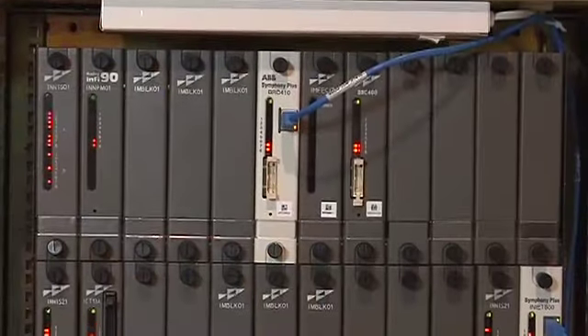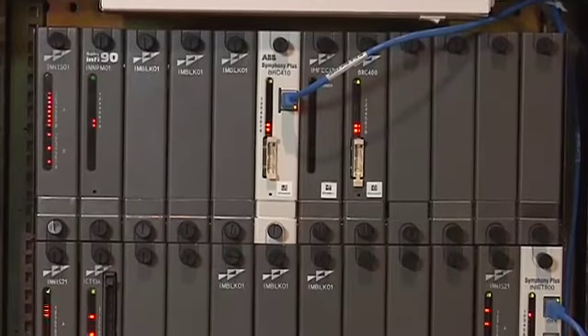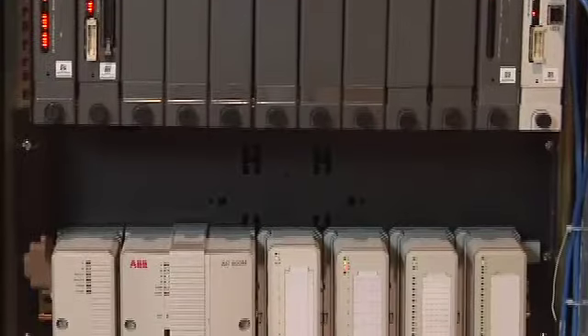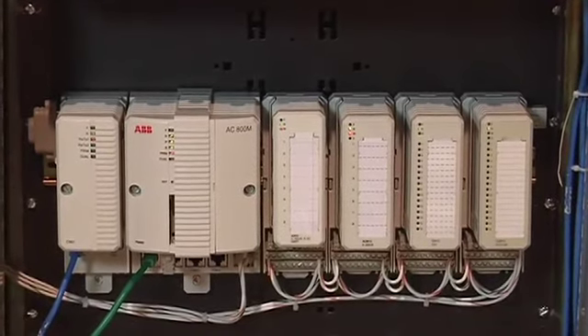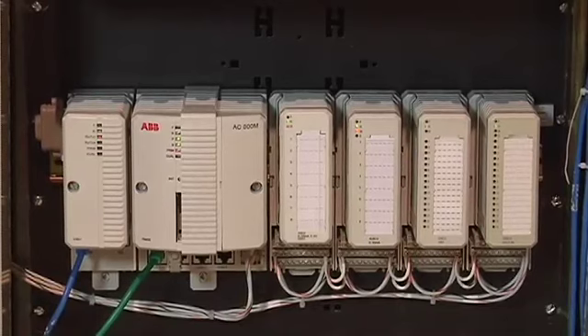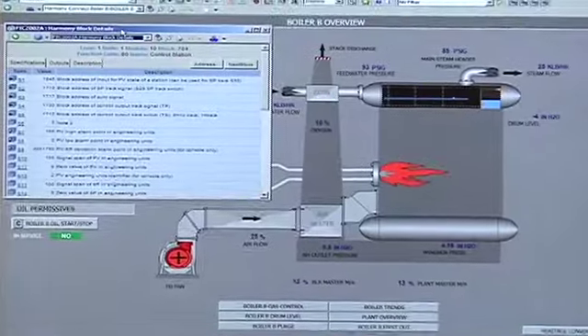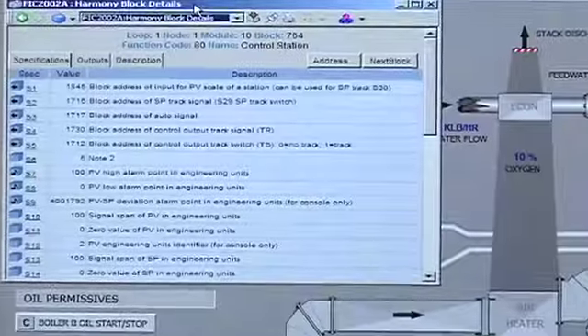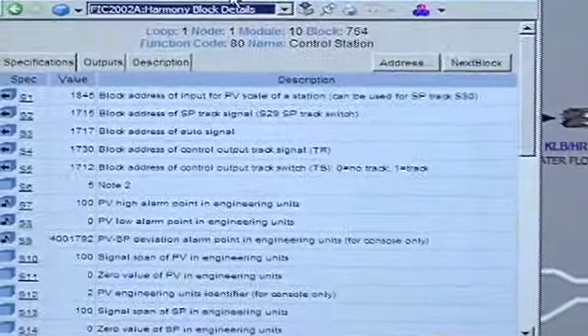There are really three things to consider when upgrading your control system. First, terminations — make sure they remain in place, because to do anything else would be very time-consuming and costly. Second, control logic — find a system that allows you to reuse that logic as is, since reprogramming or translating it is risky and costly. And finally, find an operator interface that integrates tightly with your system so you don't lose any system diagnostics or maintenance displays.